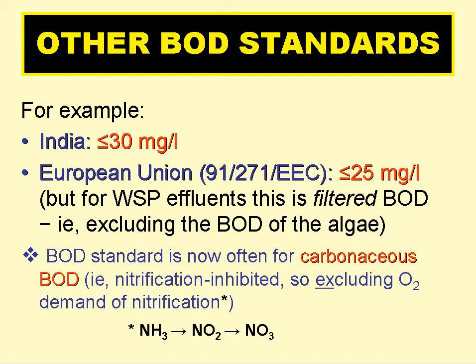Other examples of BOD standards include no more than 30 milligrams per litre in India, and no more than 25 milligrams per litre in the European Union. But for waste stabilisation pond effluents in the EU, this is no more than 25 milligrams filtered BOD per litre — i.e. excluding the BOD due to the algae in pond effluents. Generally, BOD standards are now set for just carbonaceous BOD, sometimes called nitrification-inhibited BOD, as a chemical is added to the BOD dilution water to stop the growth, and hence the oxygen demand, of nitrifying bacteria.